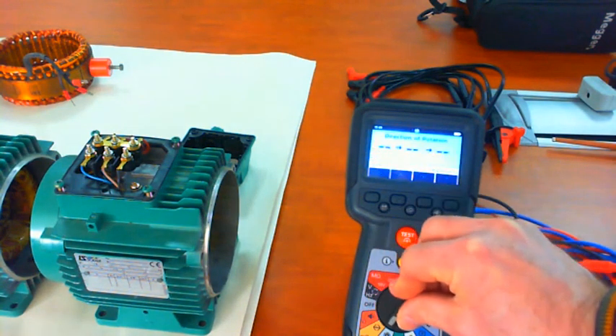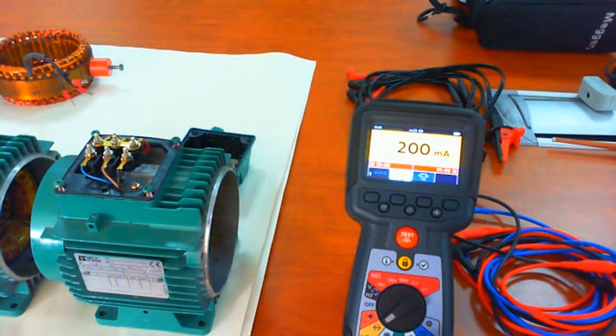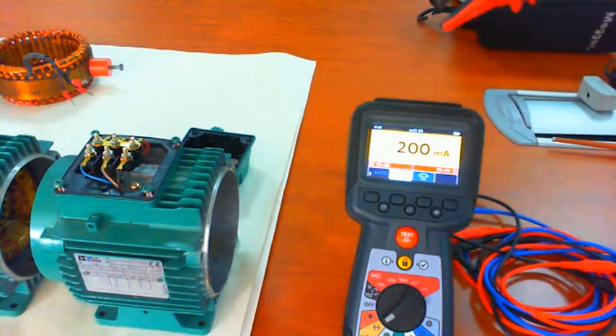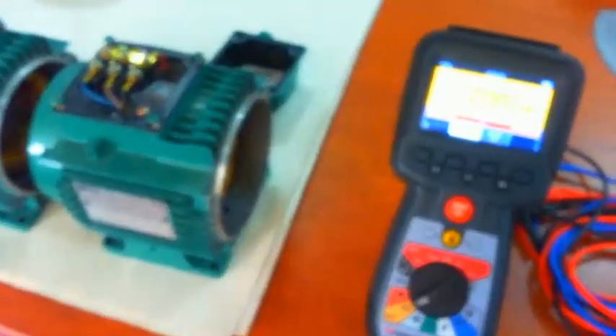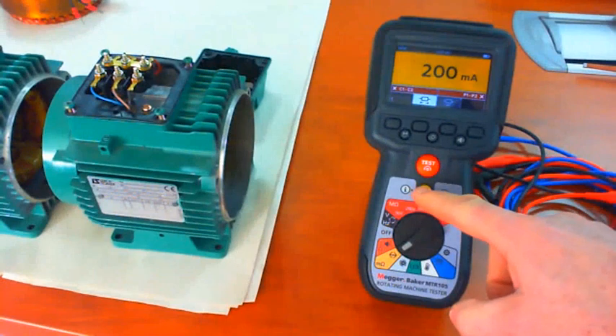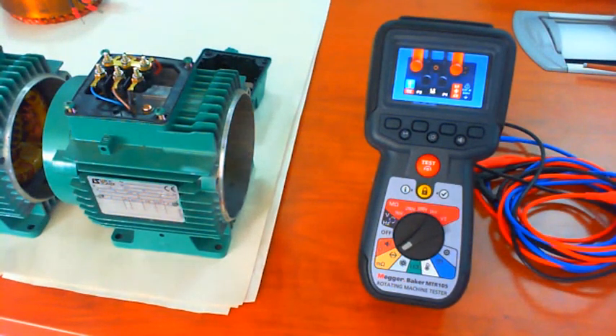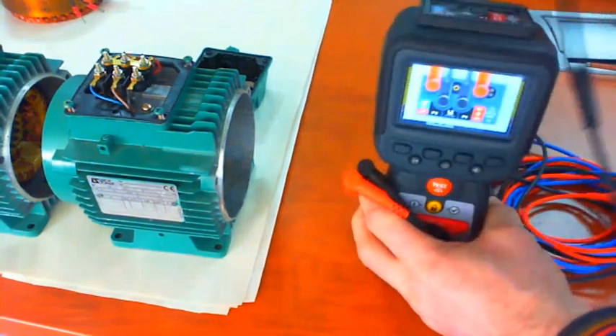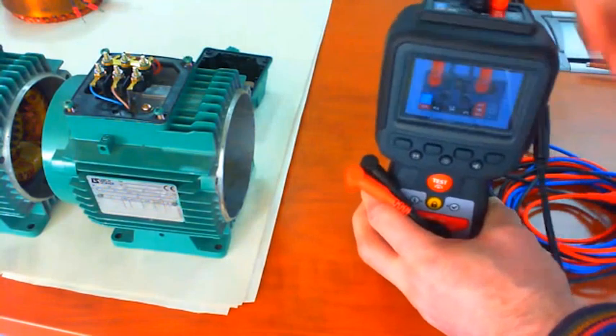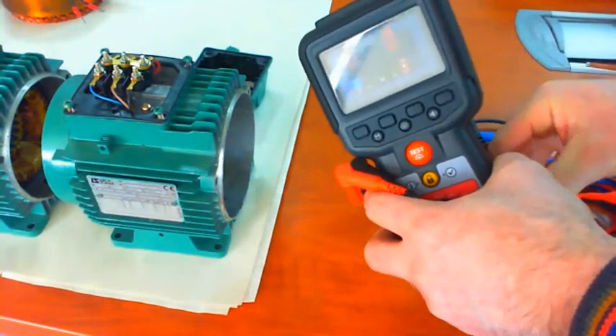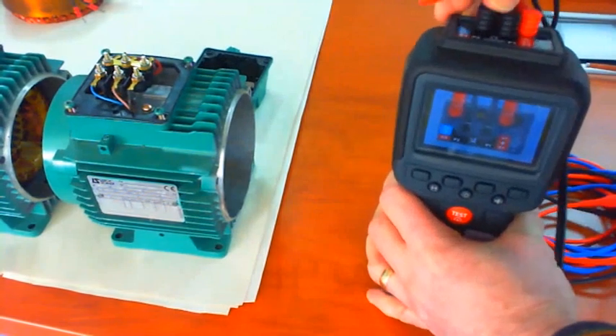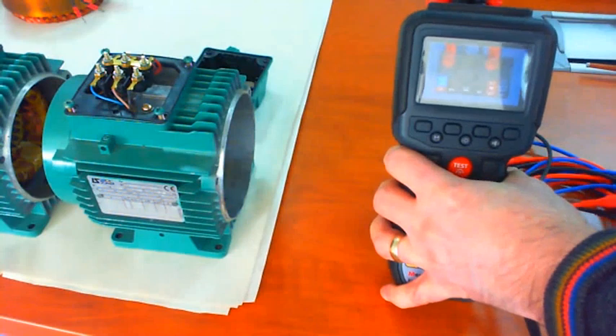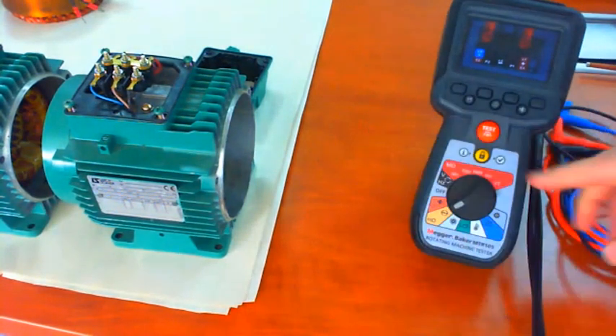So the first test we're going to do is winding resistance, low ohms measurement. For this, we're going to use our Kelvin measurement leads. Now, if we're not sure how to connect them, we can press the lock button and the screen now gives you an example of how to connect the test leads. So each clip has two connections. So we want to connect red, black, black, red. Okay. So that's our connections. We can press the lock to go back.